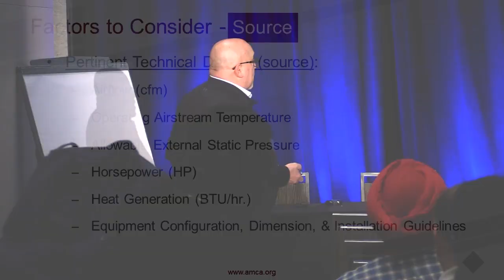If the equipment's here, are the neighbors up on a hill? Are they below? Is the noise source on a hill? What's in between the neighbors? How far away are they? I've even seen noise ordinances written, and this is the weirdest thing, but I've seen it a few times over the years, where instead of having the allowable sound levels at the property line, at maybe 5'5" average ear height above grade, mine's 5 foot, but average ear at that location, sometimes they'll say, no, we need it at a certain level because we're worried about the second story house windows being open and things like that. So you just have to look at where everything is located.